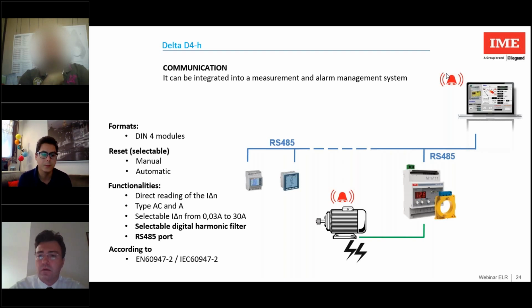As I say, if I'm not sure that it's a problem of harmonic content, I can get untimely trips instead of reacting to a real problem. So I must be sure that my circuit has a lot of harmonic content. For example, in my circuit I have an old device that I cannot change, and a minimum of differential current flow because I have old masses that no one can touch. So I am sure of what I have to do before selecting a reinforced filter.